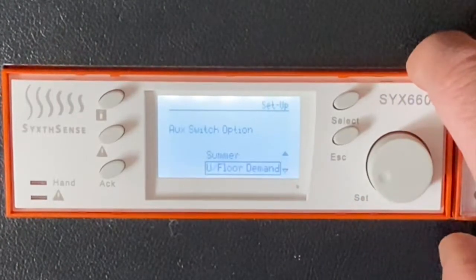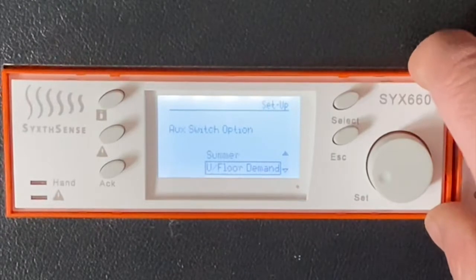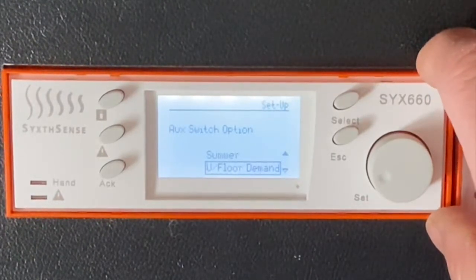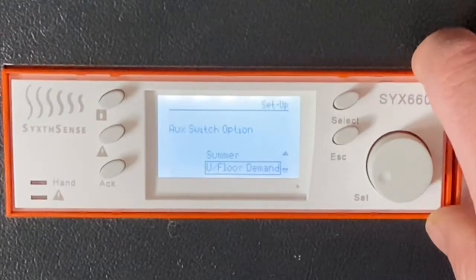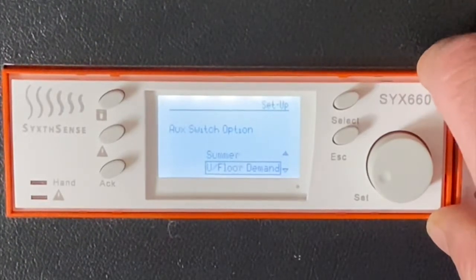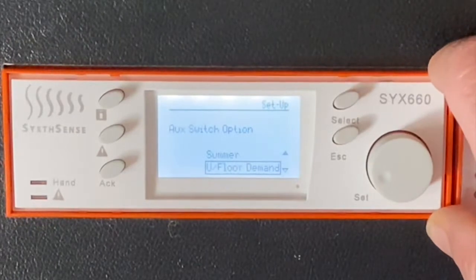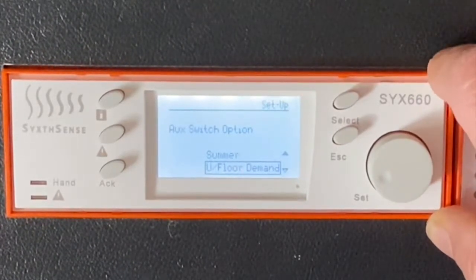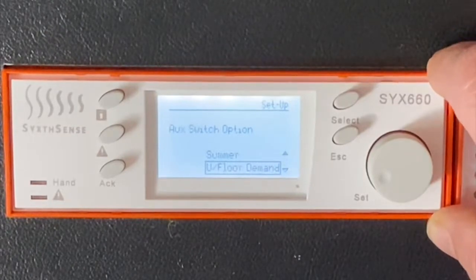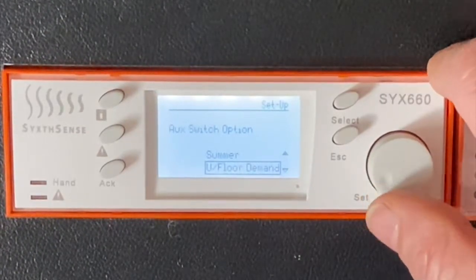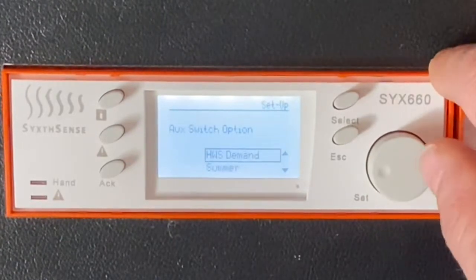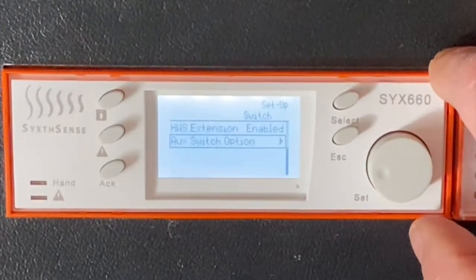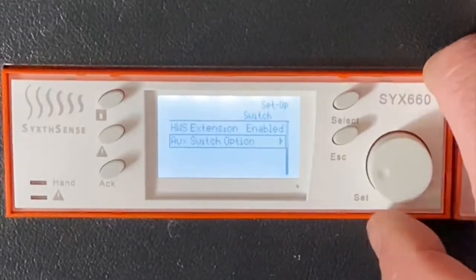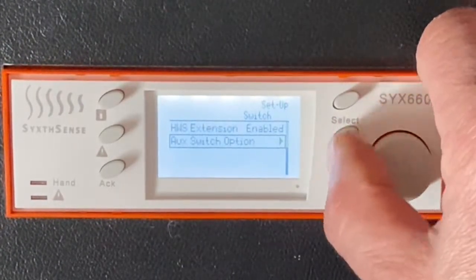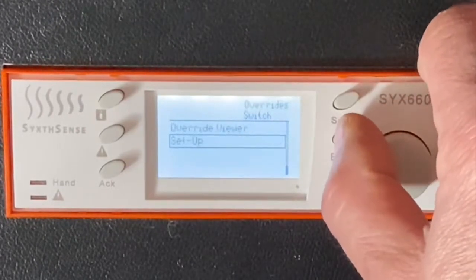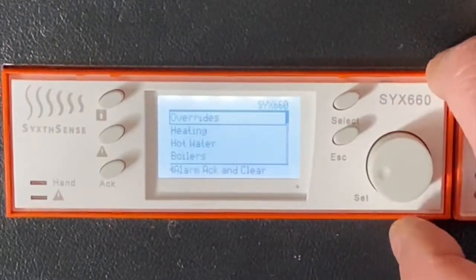Underfloor demand is where the pump output of the SYX controller is used to enable underfloor heating manifolds, and we wait for the underfloor manifolds to send a heat demand back to the SYX controller before we open the VT valve and start the boilers to service the underfloor heating circuit. So that's a nice feature. As discussed, we're going to choose hot water demand for this particular input. That concludes the options that are available in the overrides menu. We just press escape, escape and escape, and we're back to the top of the list.